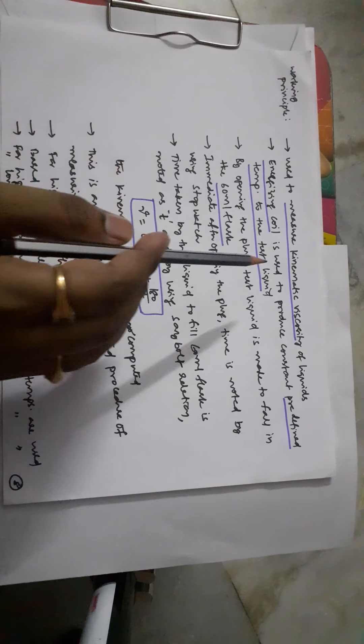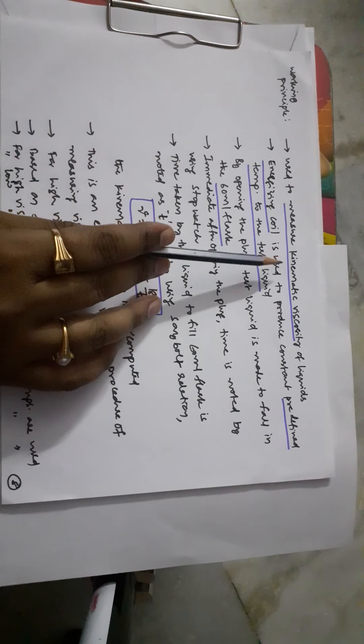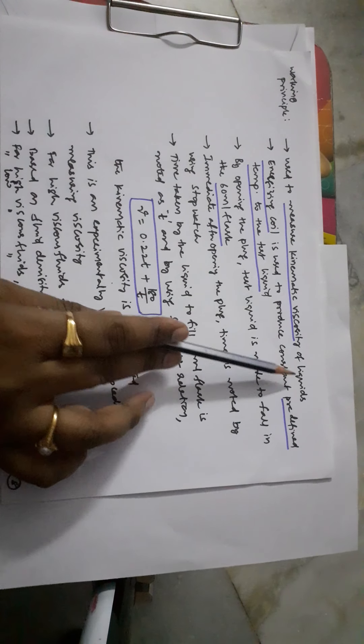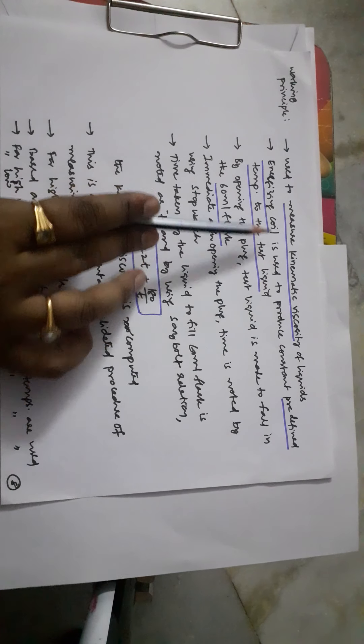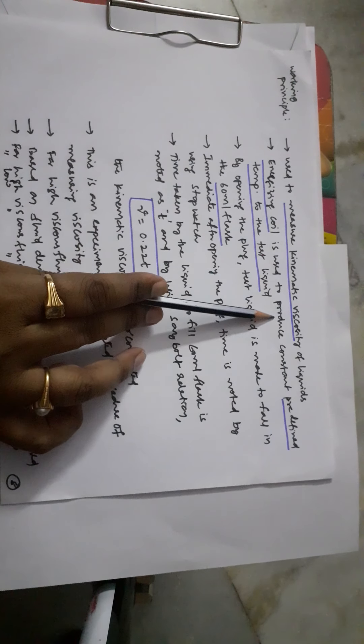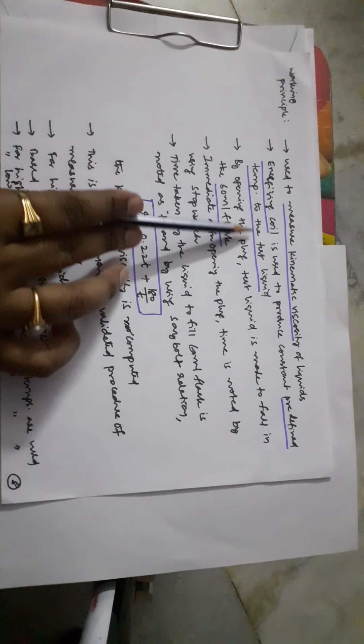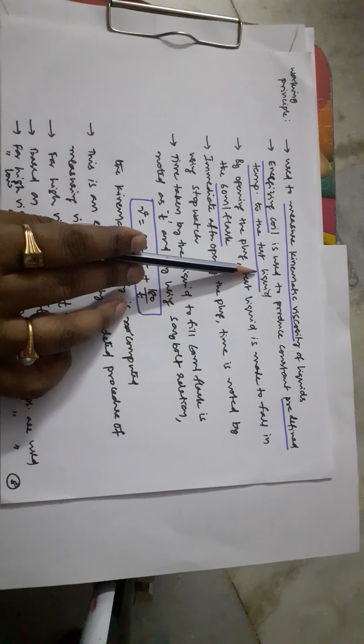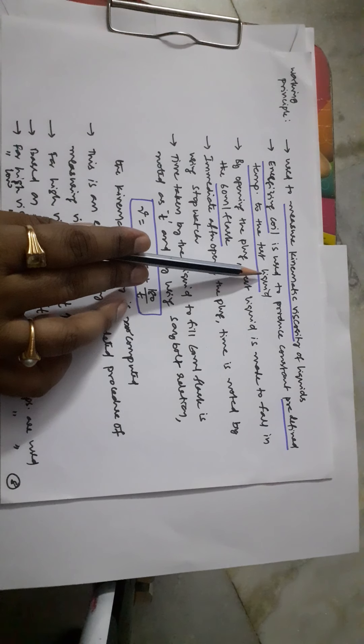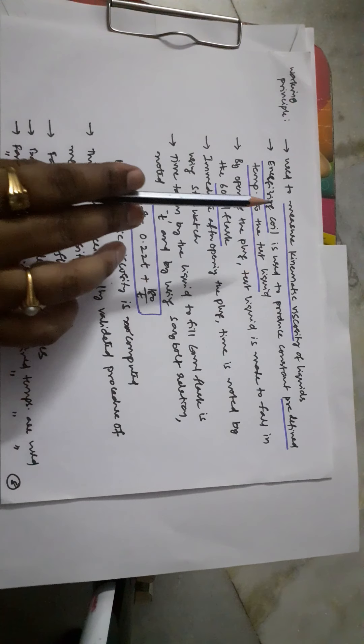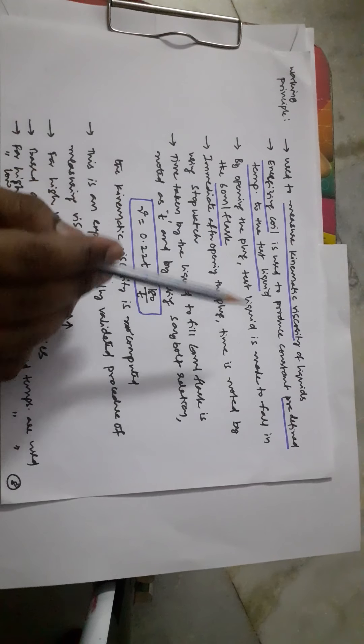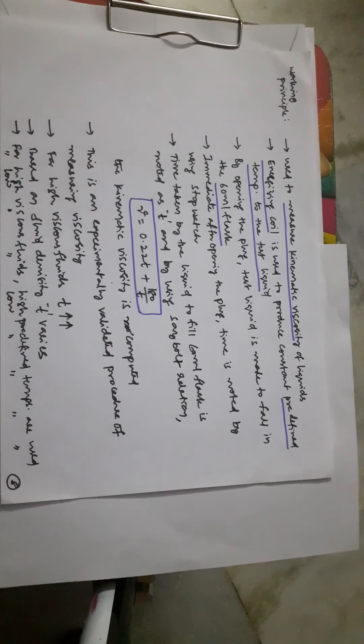Coming to the working principle: the Saybolt Viscometer is used to measure the kinematic viscosity of liquids. The energizing coil produces a constant, predefined temperature of the test liquid — the temperature can be increased or decreased and must be maintained as a constant, for which the energizing coil is used. By opening the plug, the test liquid is made to fall into the 60 ml flask.